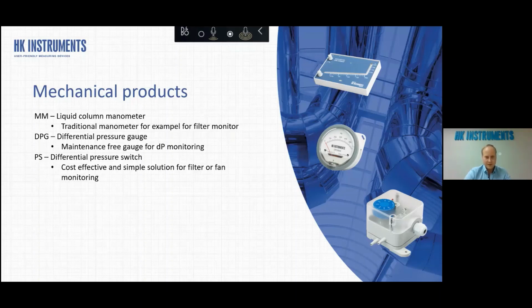And then we have the differential pressure switch, which you can see below. And it's a really simple mechanical switch, typically used to express when the filters are dirty, to give the alarm to the system. So that's basically it. Or also you can use it as the fan monitoring. So if something happens to the fan and the duct pressure drops, you can set an alarm by using this one.